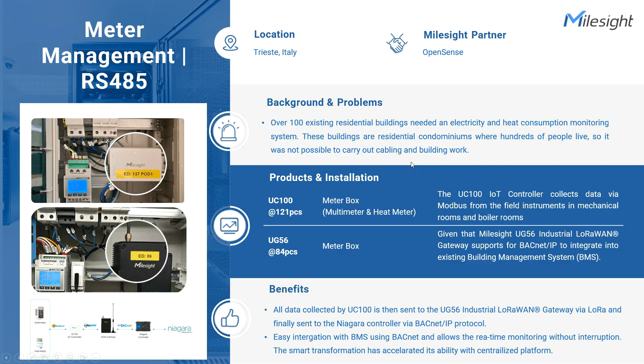Then what's the difference? Number one, the interface type. The UC100 controller features the RS485 interface only, so it converts Modbus protocol to LoRaWAN or to Milesight D2D, vice versa. While UC300 features more industrial interfaces, besides the RS485, the industrial port RS232, digital input and output, analog input including 0 to 10 voltage, 4 to 20 milliamps, PT100 RTD temperature monitoring are all available in UC300.